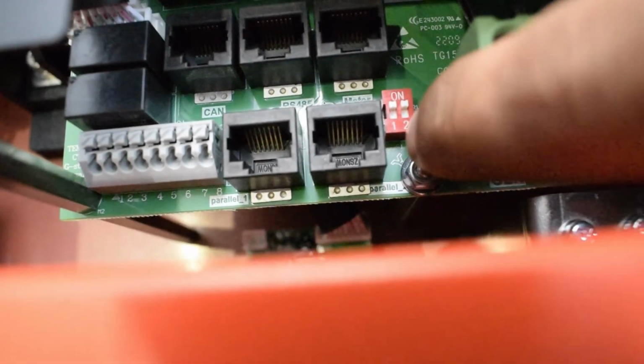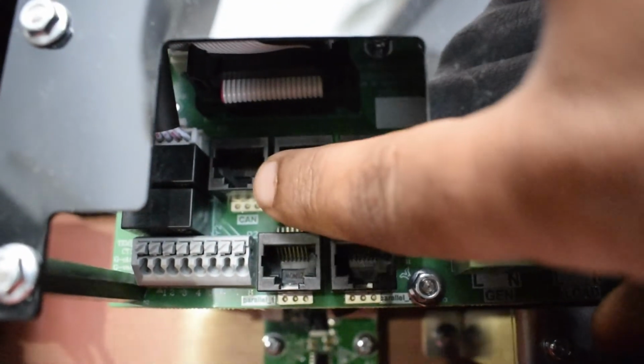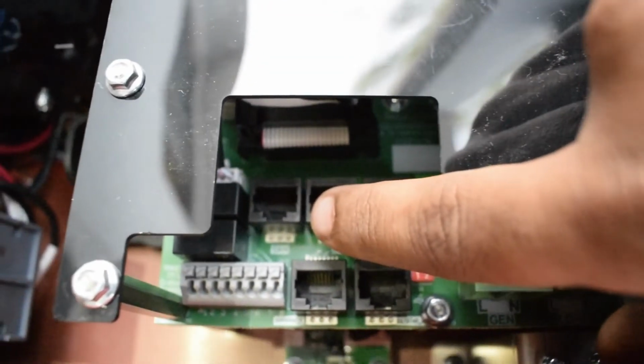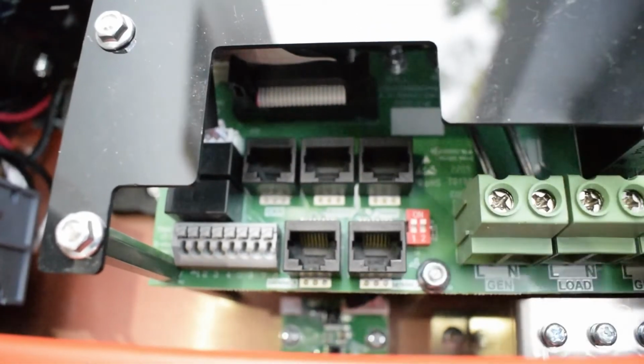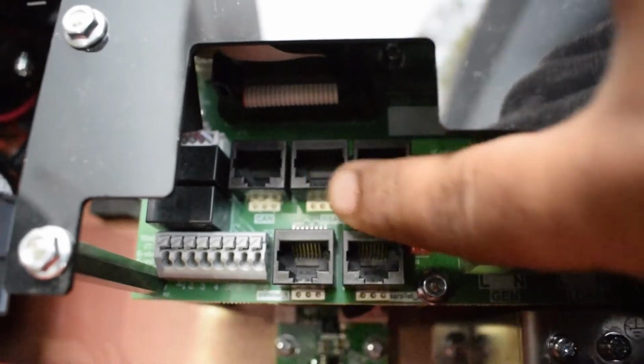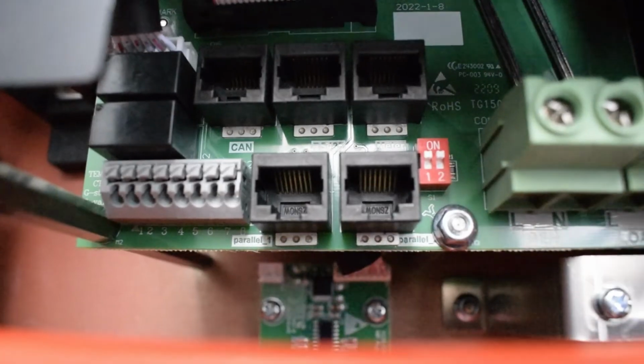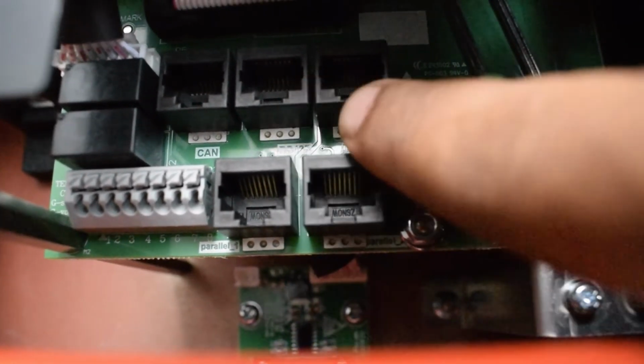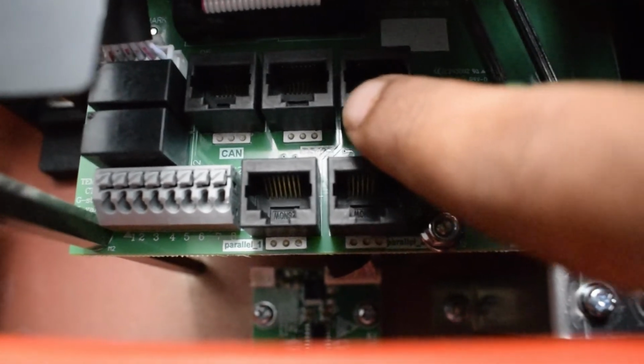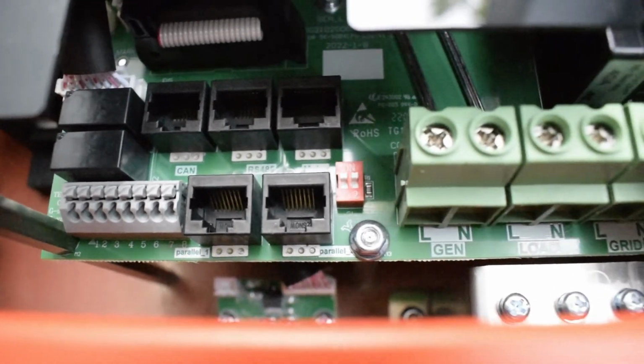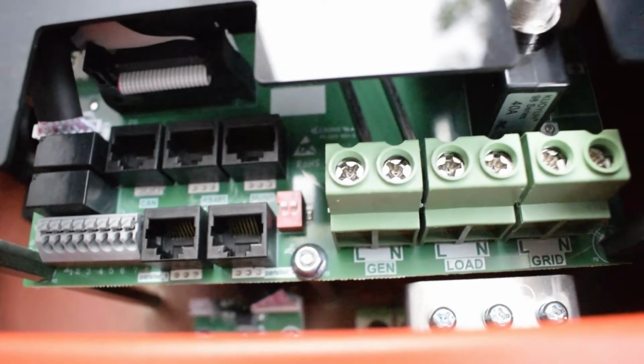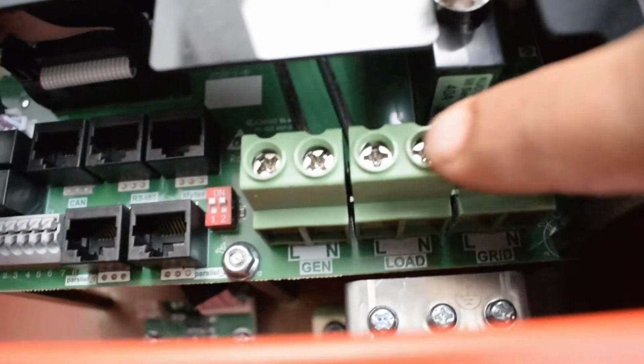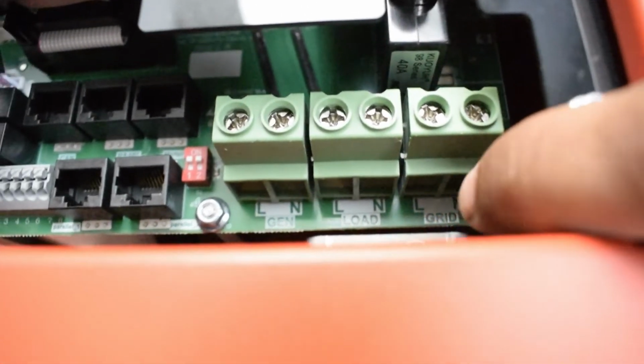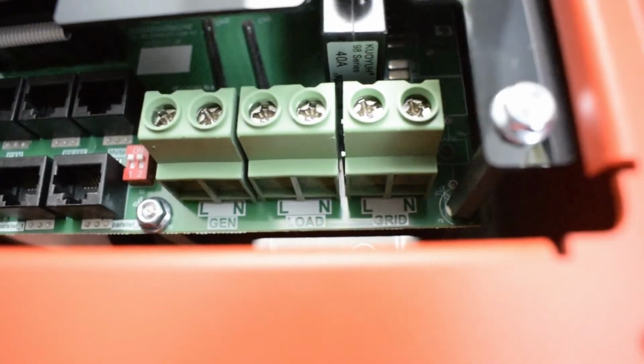Okay, and from these dip switches we can make different parallel connections. And the top 3 ports, the most left is the lithium BMS card function for controlling the lithium based batteries for their safety and controlling of their power, and these 2 ports are for RS485 CHINT power meters. They can be utilized. We will make another episode or part of this inverter solution in which we will show the power connection of the inverters. And the remaining major 3 ports are for generator, load and grid. These 3 ports can be utilized for different purposes.